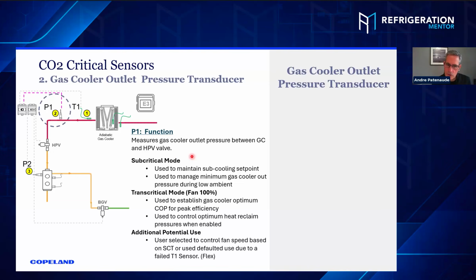Well, it measures the pressure of the gas cooler out, but in subcritical mode, it's used to maintain the subcooling set point. The high pressure valve moves, it measures it and readjusts to make sure that it maintains that subcooling set point. Also, in low ambient, there's a minimum gas cooler pressure that it wants to maintain, and it's going to act like a holdback valve in the winter, just like any HFC system. When the pressure gets too low, it's going to hold back to maintain that pressure, right? So that's its function in subcritical mode.